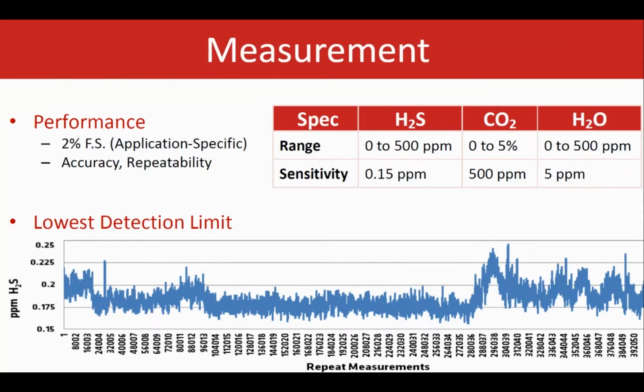This one here is a nice summary showing the main measurements for the AccuLase. We can measure all three components of our interest in one single unit using only one single cell. So for the H2S, we can measure 0 to 500 ppm with an LDL of 0.15 ppm. For the moisture, we can do 0 to 500 ppm with an LDL of 5 ppm. And for the CO2, 0 to 5% with an LDL of 500 ppm. So these are all within our standard accuracy. Again, it's important, and I keep emphasizing this, all in one single cell, one unit.